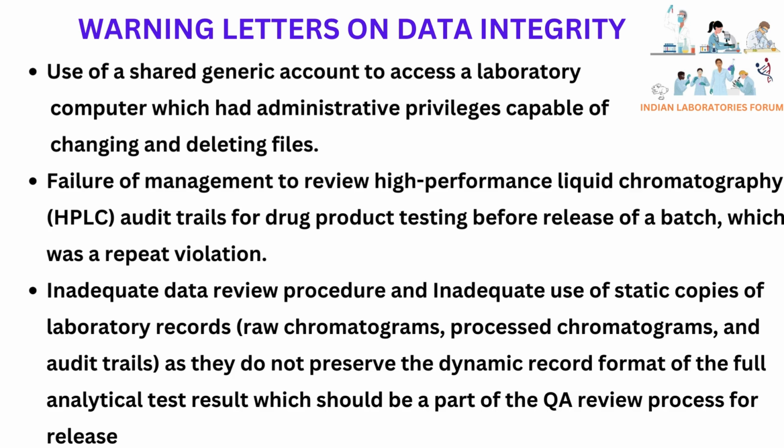Inadequate data review procedure and inadequate use of static copies of laboratory records, such as raw chromatograms, processed chromatograms, and audit trails, as they do not preserve the dynamic record format of the full analytical test result, which should be a part of the QA review process for release.